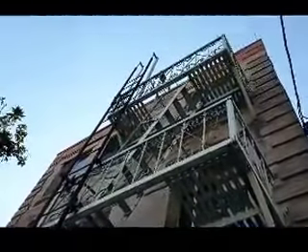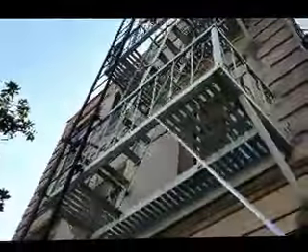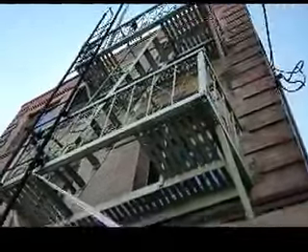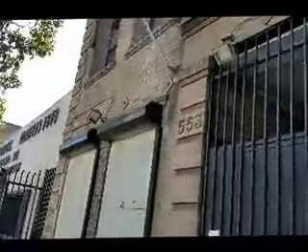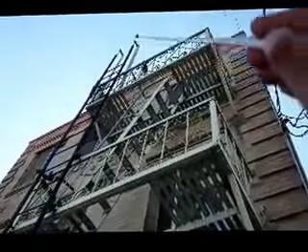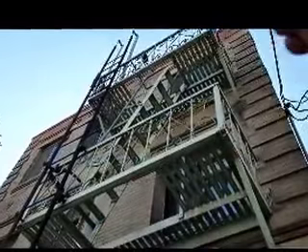I'm here at 553 Stanford Avenue in Los Angeles, California. As you can see, I just made my way down. I performed a fire escape inspection for this platform and the staircase with the treads and railings to the uppermost platform, eventually with the fire. This is the balance ladder that doesn't go to grade. It does not drop 2 to 3 feet per second. It has some repairs needed, maybe a full replacement, meaning that this hydraulic oil balance ladder is no longer in operational condition, and given its age, it is recommended you replace it in full.